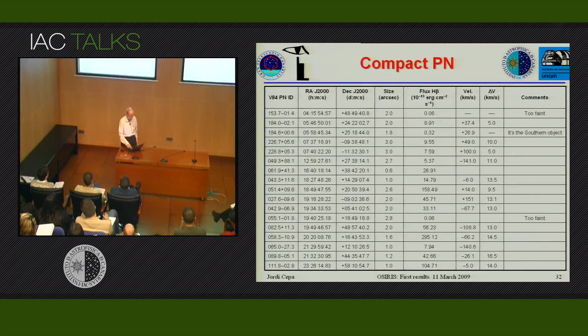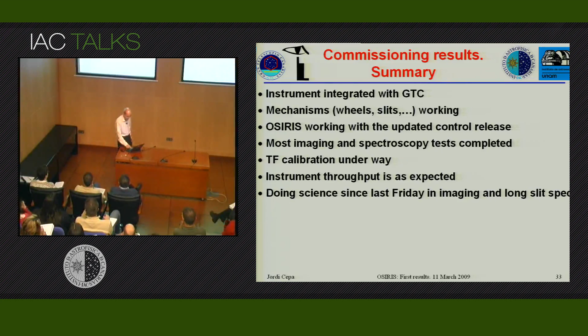Okay, which are the pending tasks? We encountered some technical problems. For example, it's interesting to say that even for a non-cryogenic instrument, or perhaps in spite of being a non-cryogenic instrument, temperature affects the mechanisms. The working temperature in the laboratory was about 20 degrees or so, and when going to the dome, the temperature was between 5 and 10 degrees. Then it was necessary to give more torque to the motors in order to move the mechanisms. So we had to slightly reduce the speed in order to increase the torque, and everything was solved, but of course it took a while to realize that.